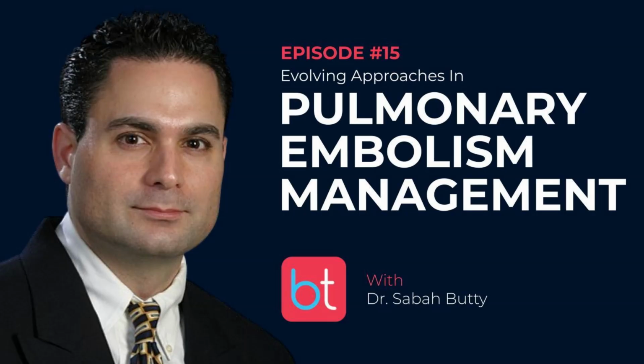Then the second thing that I'm going to look at when I'm considering a device is how efficient and how effective is it? And then thirdly, we can talk about blood loss or the necessity for it or blood return, however you want to look at it. To me, those are, as I listed, the most important things to consider. So when I look at a thrombectomy catheter, the reality, and this is my opinion, is that I believe all these catheters will have adequate suction, whether it's syringe-based, vacuum-based, or handle-based with Alpha Vac. They're going to have enough suction power to remove that embolic debris. I think the question becomes, how do we do it? How do we get that angiogram that looks good at the end of the case? And that's what matters to me the most.